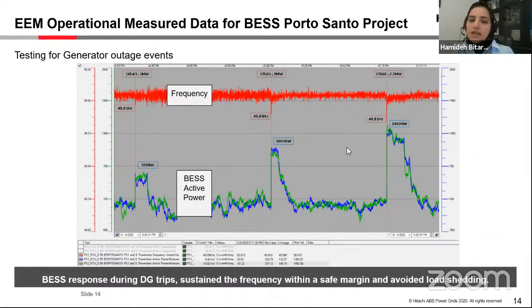You can see that the frequency dropped through these events, and the battery responded to these generator outages. The battery compensated for the generator outage and provided support for the frequency excursion, sustaining the frequency within sustainable margins. So these are real operational data from our Porto Santo project where we provided the best solution for EEM utility. EEM is the utility that supports the islands of Madeira and Porto Santo.